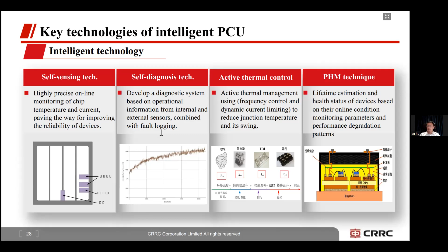Self-perception is an important part of the intelligent PCU. We used chip-integrated current sensors, which had a response time for overcurrent and short circuit protection of less than 2 microseconds, even faster than traditional methods, enhancing the safety of the devices. Meanwhile, high voltage isolation, sensing, signal extraction, and current ratio posed huge challenges.